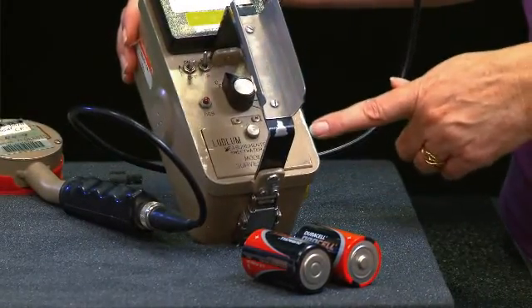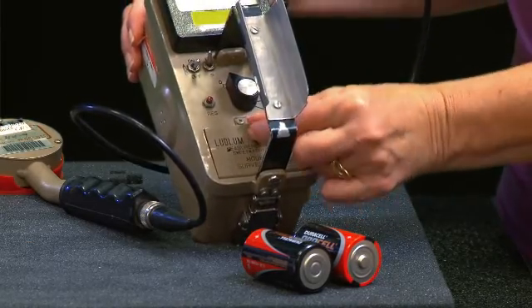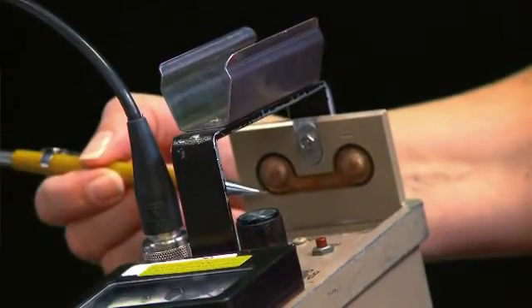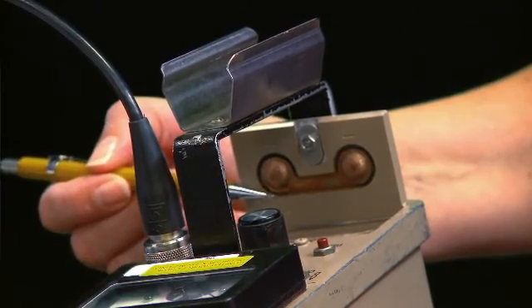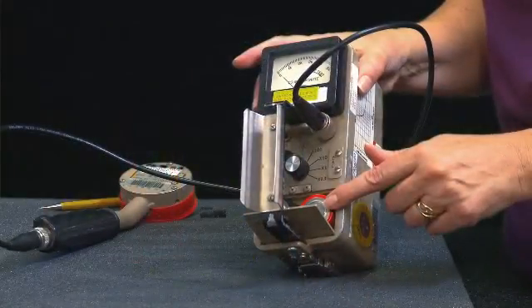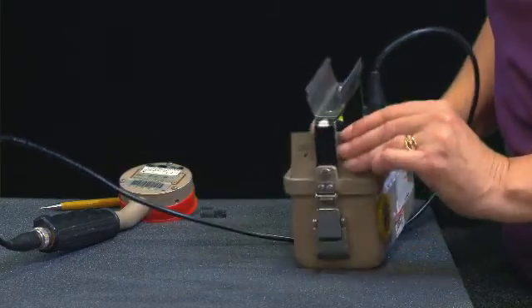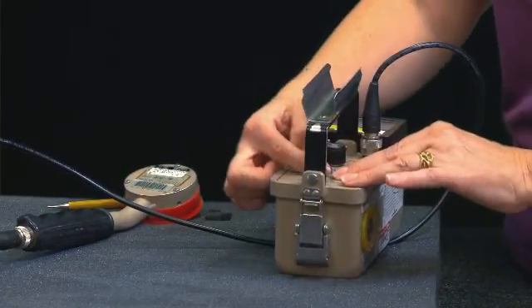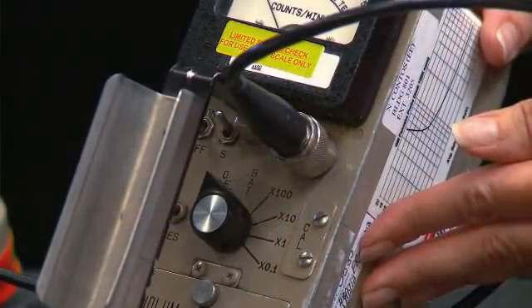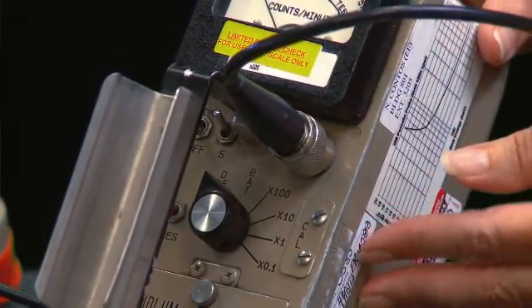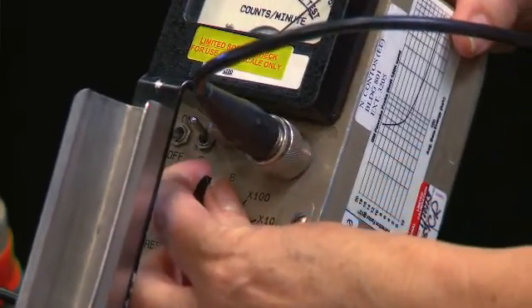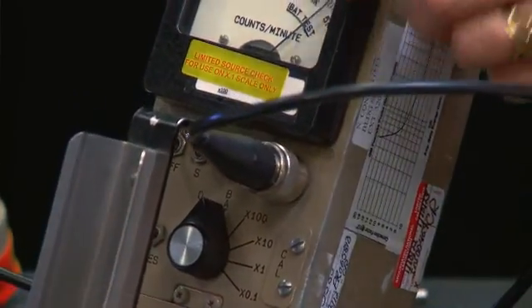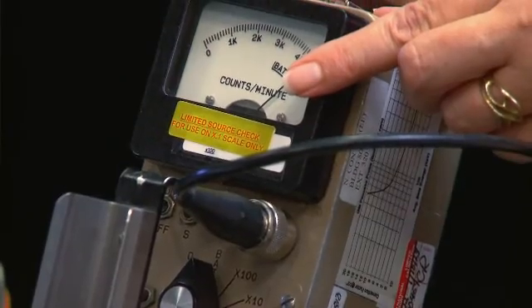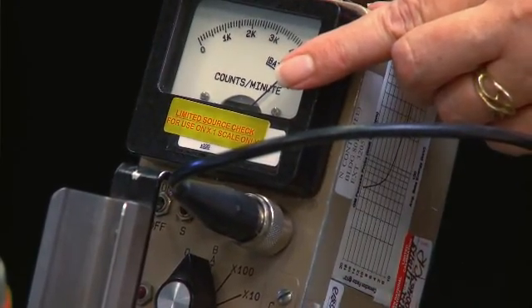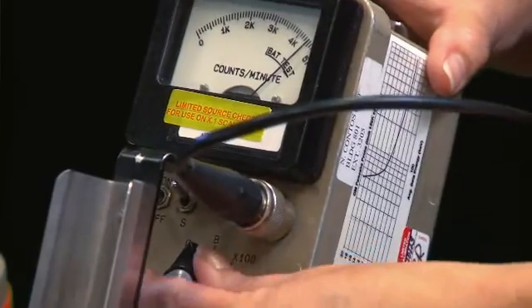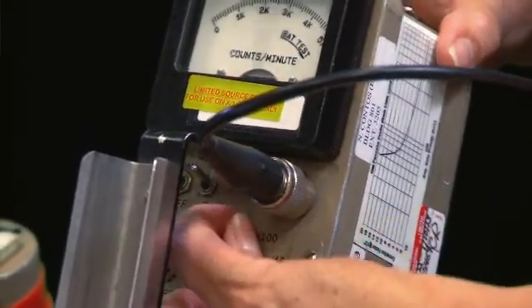Next, open the battery compartment by turning the thumb screw and install 2 D batteries. Note the polarity indicated inside the compartment's cover. With the batteries properly inserted, close the cover and lock in place. Note that the switch has multiple positions. Move the dial from off to bat. The needle should register within the bat test range. Do not proceed if the batteries are not in good condition.